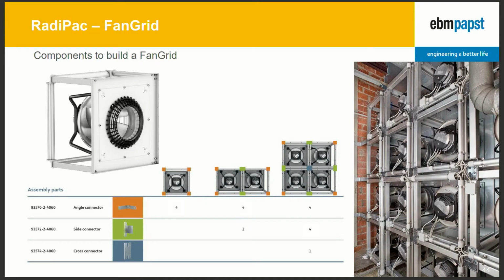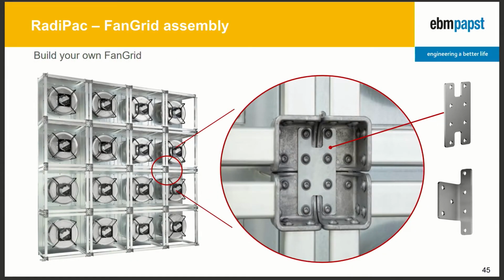We create such a product by using aluminum struts and mounting our standard spider mount fan inside, and then these cubes can be stacked. We also offer some sheet metal parts that are put in between the different fans just to fix them. And here you can see a retrofit installation using this kind of design. So here is another one. Very easy. The fan itself is the separation between pressure side and suction side.